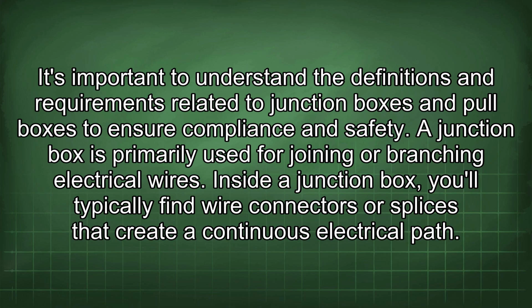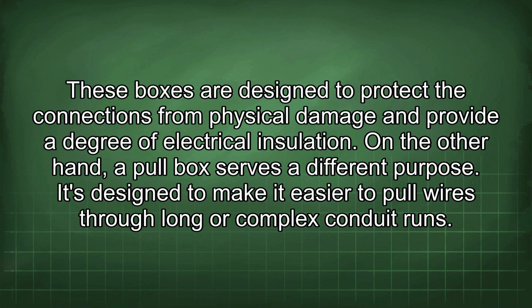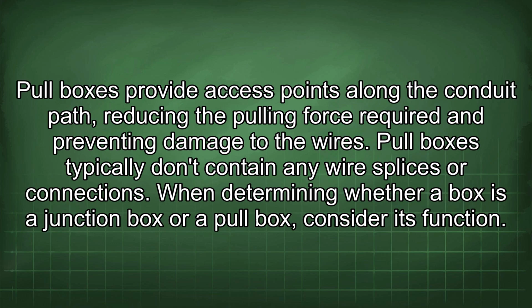A junction box is primarily used for joining or branching electrical wires. Inside a junction box, you'll typically find wire connectors or splices that create a continuous electrical path. These boxes are designed to protect the connections from physical damage and provide a degree of electrical insulation. On the other hand, a pull box serves a different purpose. It's designed to make it easier to pull wires through long or complex conduit runs. Pull boxes provide access points along the conduit path, reducing the pulling force required and preventing damage to the wires. Pull boxes typically don't contain any wire splices or connections.